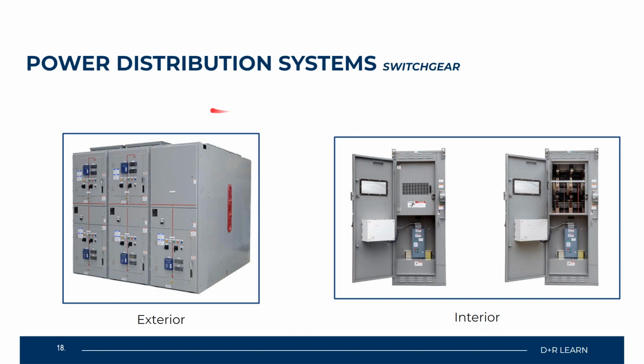Now, as we can see here, one part of our power distribution system is a component we call switchgear. Switchgear is a system with a combination of circuit breakers or fuses, which is used to isolate, protect, and control electrical equipment from any type of defective condition. One of the uses for this switchgear is to transfer power within your site. A lot of the time you will find that electricians are mainly the ones working on this type of system. You will not find an HVAC technician or anyone other than a qualified electrician working on switchgear.